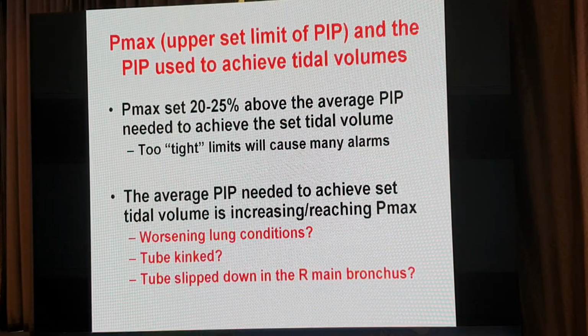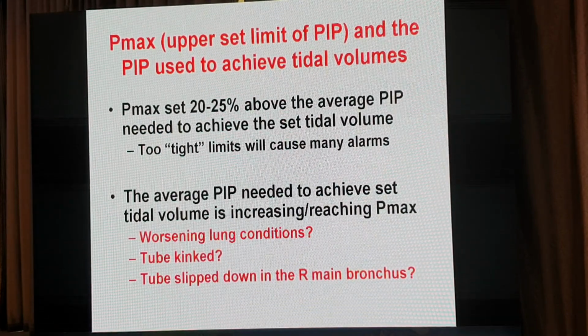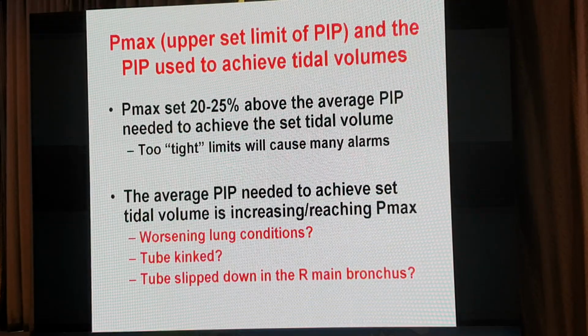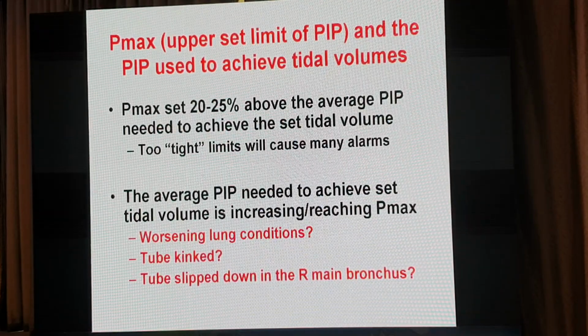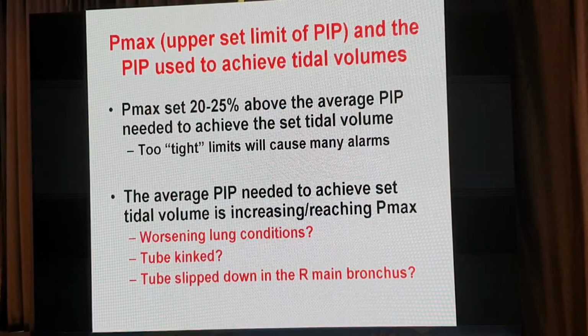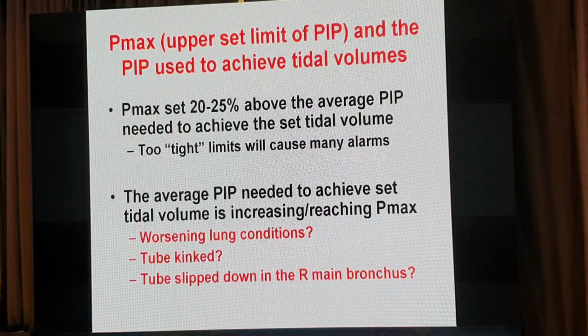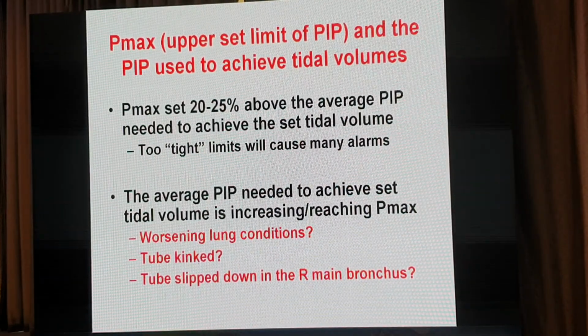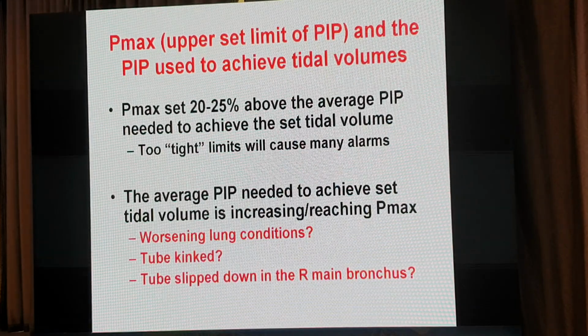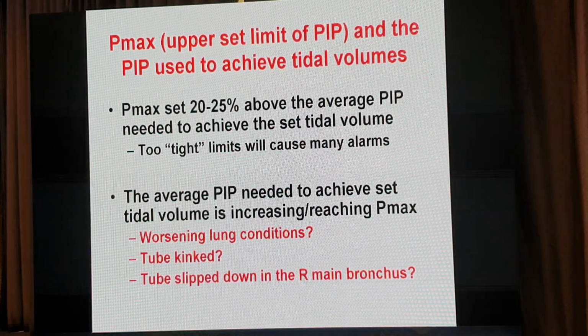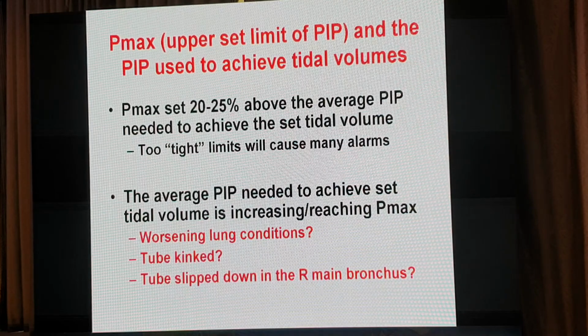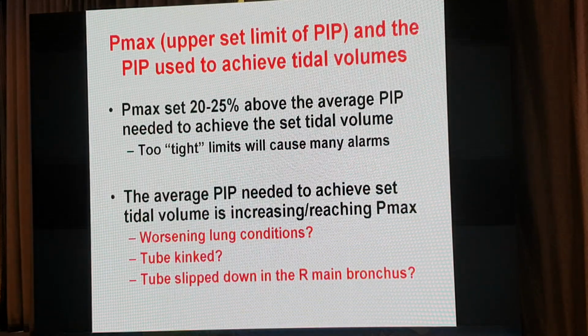This is a kind of fine-tuning you get used to. But if the alarm limits or the Pmax limit are set too close, people get fed up, because people hate alarms, and they're also very distracting for staff in the neonatal intensive care unit. So try to find a proper Pmax setting for volume target ventilation.